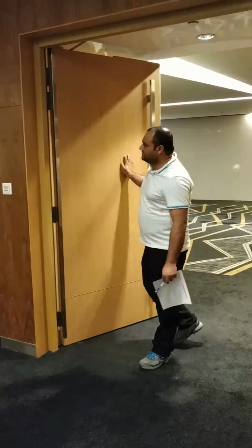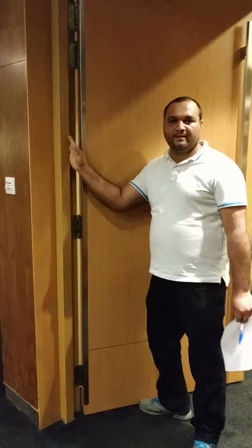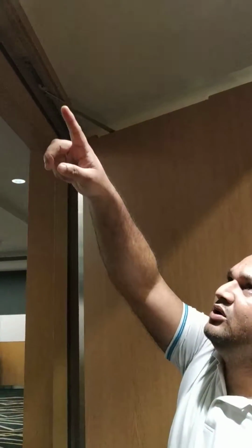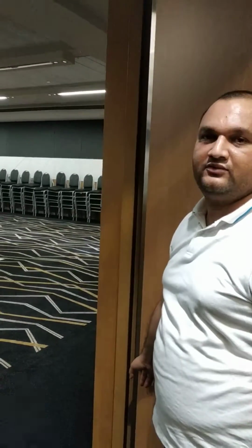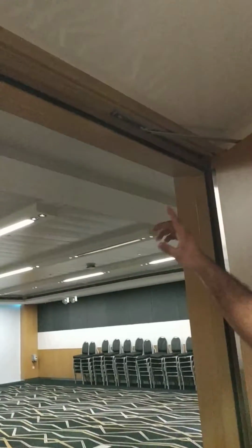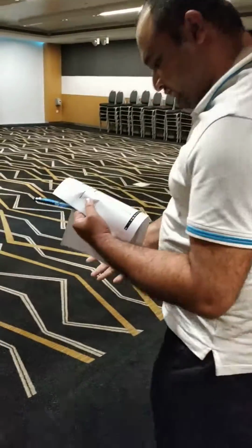Then all these doors are fire rated and also soundproof. We have to check this soundproof. Make sure visual check. All the soundproof, the black color one, no turn off, no tear off. All must be good. If any is torn off or turned off, we must highlight. We have to highlight all this black color soundproof seal. Okay, now we go to the next round.